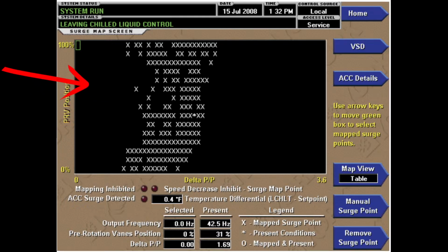You do need to be in a service mode, and then you have to input a special password to get into the surge map. It's a whole process to get in here, but there'll be a little O that floats around. So this green box is your indicator. There's an O. Let's see if we can find the O on here. This example may not show it. No, it's leaving water control. It should be on, but we don't see it. Huh. Either way, oh, there it is, right there.